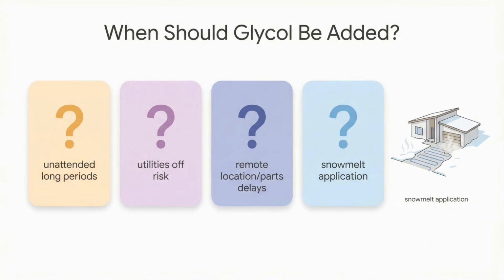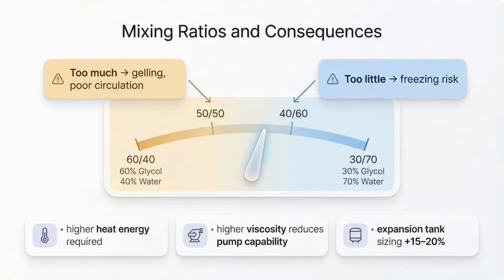The module highlights 4 decision factors: whether the building is left unattended, the risk of utilities being off, how long repairs might take due to location and parts availability, and whether the system is a snowmelt application. The glycol-to-water ratio must follow manufacturer specs. Common ranges are roughly 60-40 to 30-70. Too much glycol can gel and stop circulation. Too little may not protect at low temperatures. Glycol also reduces efficiency. It needs more energy to heat, it's more viscous so pumps work harder, and it expands more than water, often requiring expansion capacity to be increased by about 15 to 20%, depending on the mix.